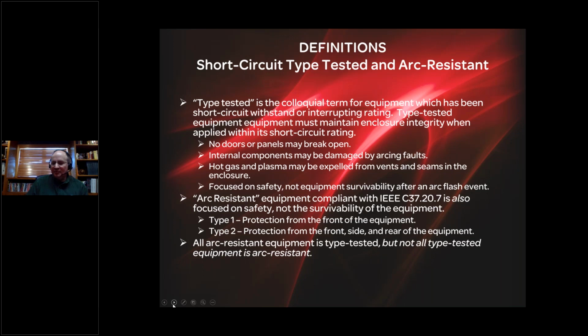And all the major manufacturers I'm aware of, I'm sure there are exceptions out there, produce type 2 equipment when they produce an arc-resistant design. And all arc-resistant equipment, again, by definition, is type-tested. But of course, not all type-tested equipment meets C37.20.7.